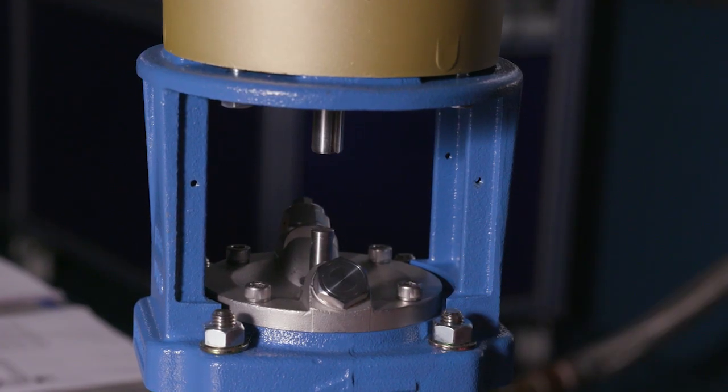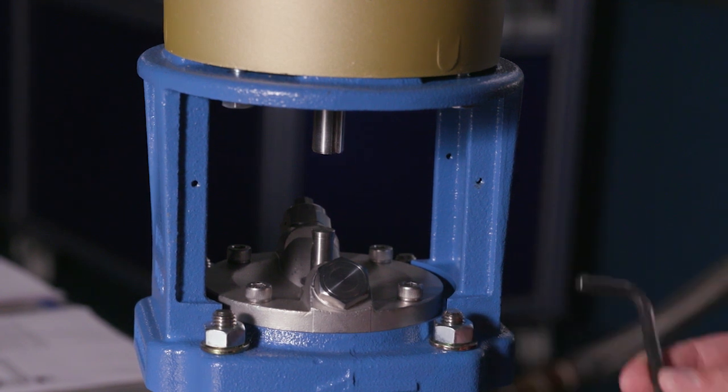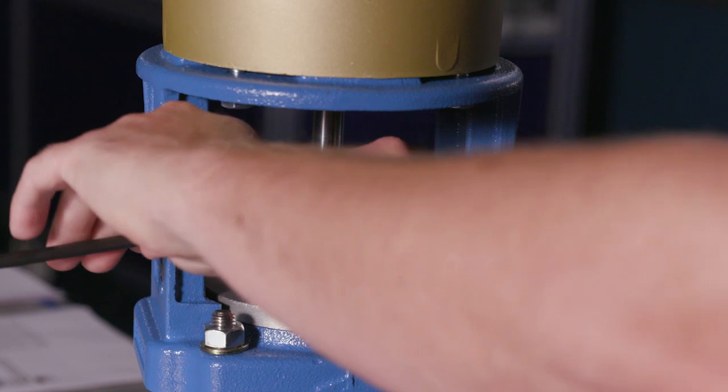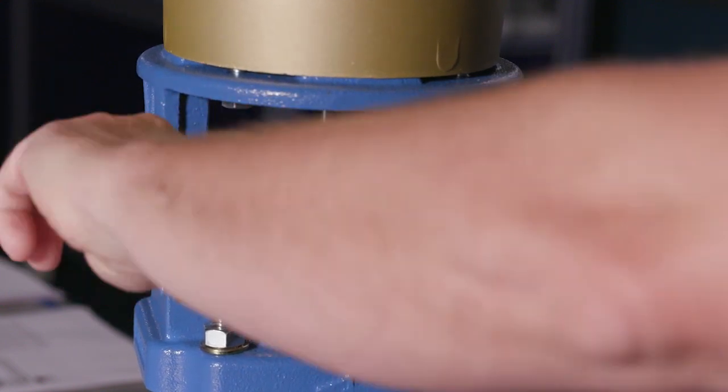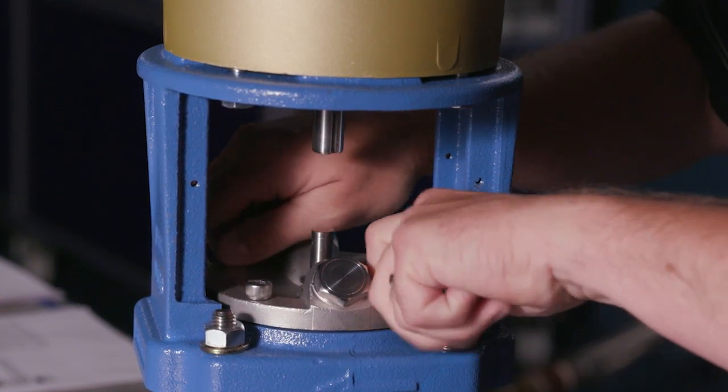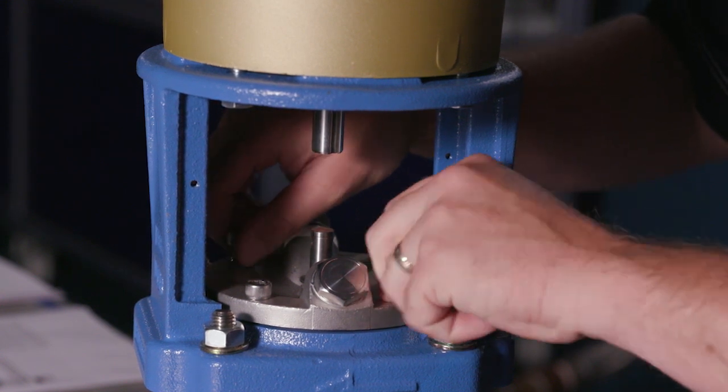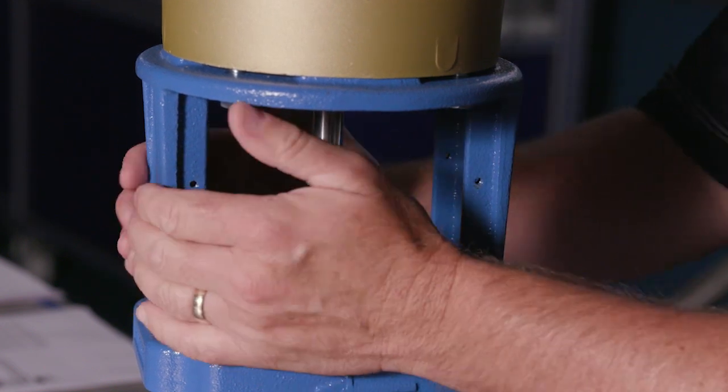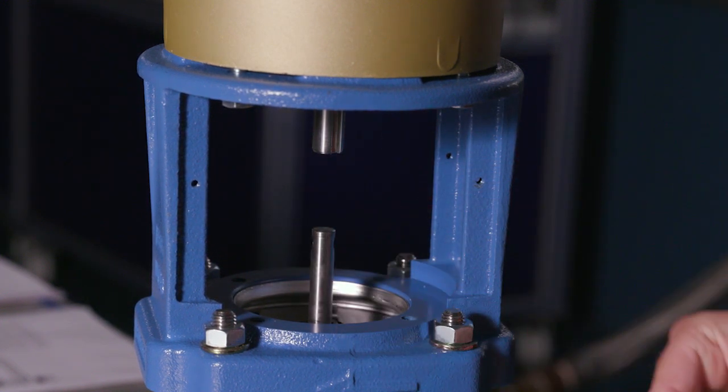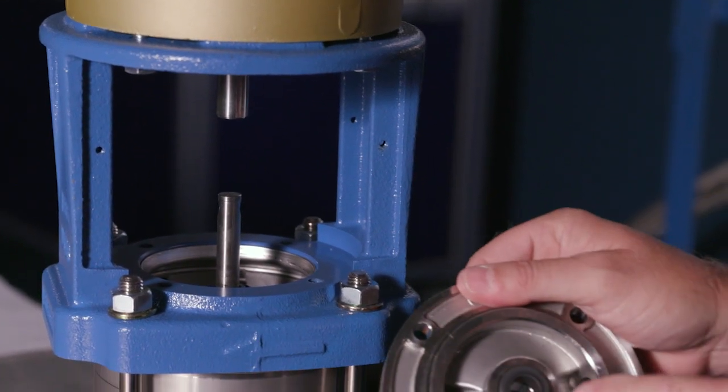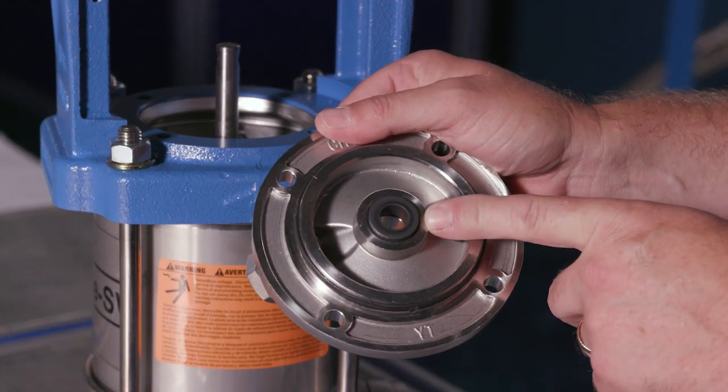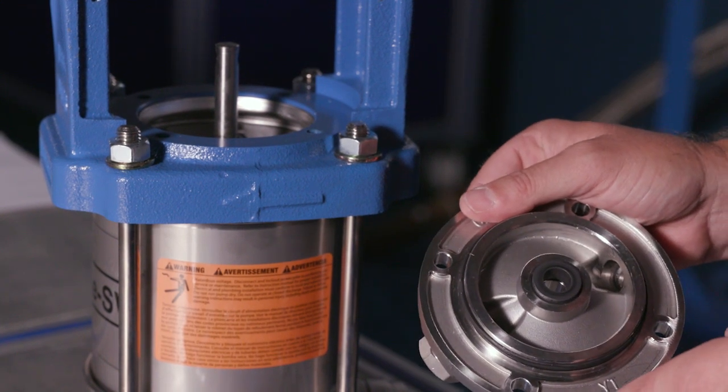Next, we're going to remove this seal gland or seal plate. Again, you need a six millimeter, so we're going to go with the Allen here. We'll notice here we have a portion of the seal, and this is the stationary portion of your mechanical seal, and inside we have the rotary section attached to the shaft.